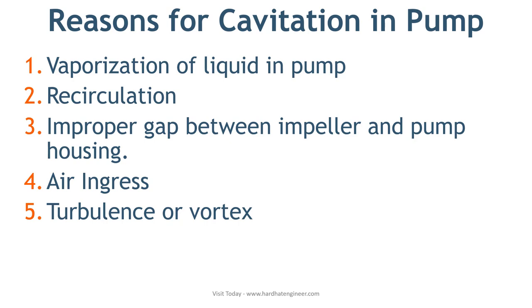As a rule of thumb, NPSH available should be 3 feet more than NPSH required. The second reason for cavitation is recirculation. Recirculation happens when the discharge is restricted — when liquid cannot exit the pump, it starts recirculating, leading to a rise in liquid temperature and creation of vapor bubbles. The third reason is an improper gap between the impeller and pump housing. If that gap is very low, liquid passing through at high velocity will lead to cavitation.